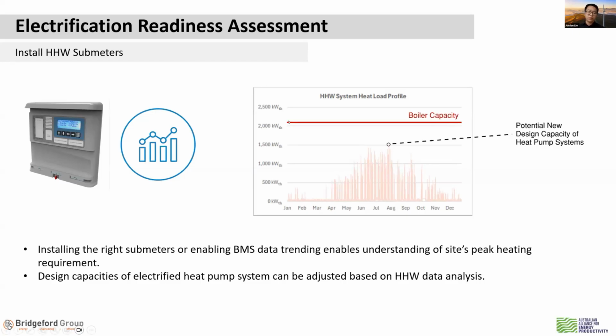but it's going to be a balancing game too, right? Because, let's say for a high-rise office, you don't necessarily have sufficient structural loading to install your buffer storage. The additional structural works required to install the cheaper buffer storage can actually increase your cost too, and in that event it's cost neutral compared with just installing the heat pumps. But one important thing to note is that if you install a heat pump system, you typically need to install buffer storage anyway to prevent the heat pump from short cycling. So what you probably want to assess is, with the minimum buffer storage requirement, how much heating capacity does it already offer, and then go from there.